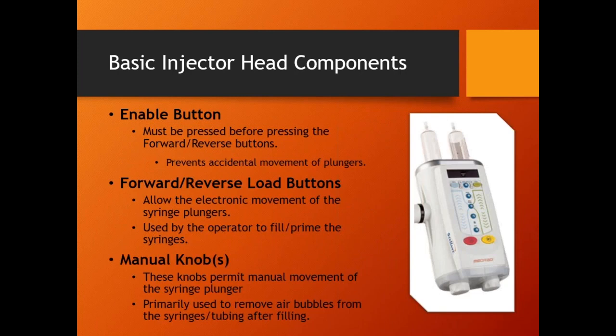Yeah, on this particular model, the enable button. Pretty much all contrast injectors have this. Again, there's one model that's the total opposite of this. They don't want the operator, especially if we're hooked up with the patient, to grab the injector head, tilt it or something, and hit one of the forward or reverse buttons. That's what these strips right here are. And then all of a sudden we're moving the syringe on the patient. So before you can use the forward reverse buttons, there's a button right here that's called the enable button. Pretty much all contrast injectors have this enable button.